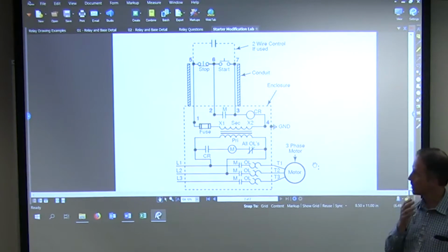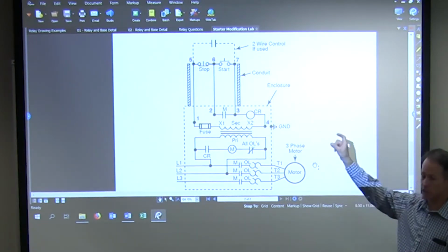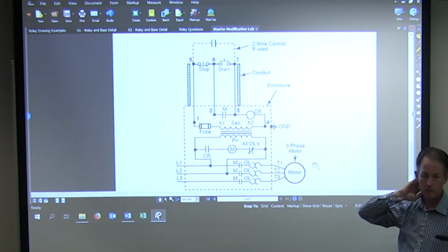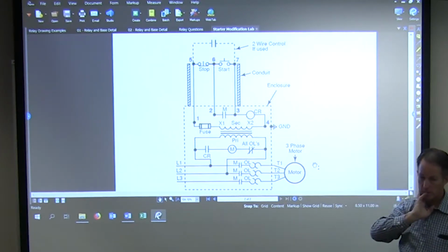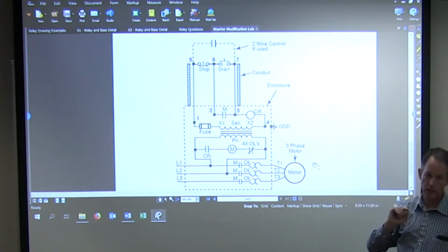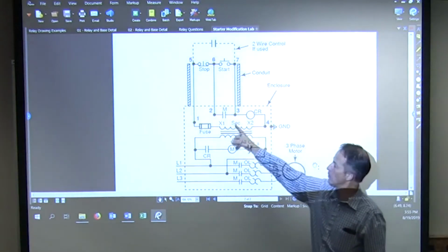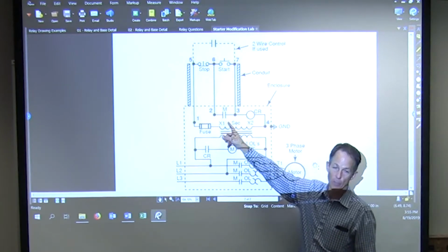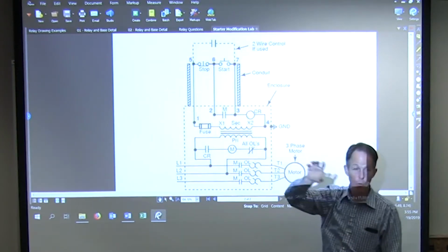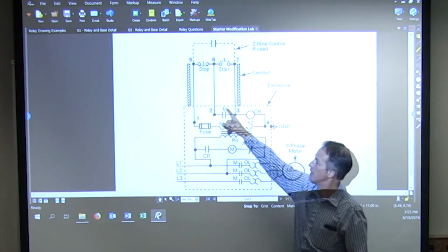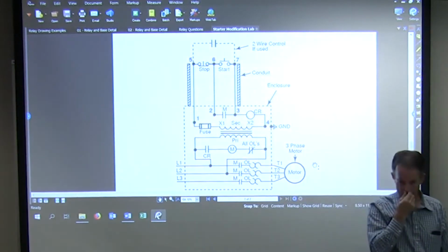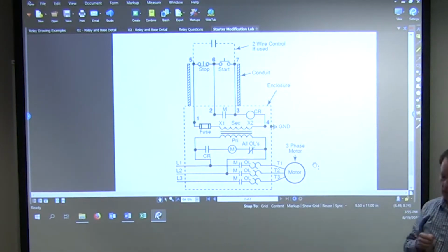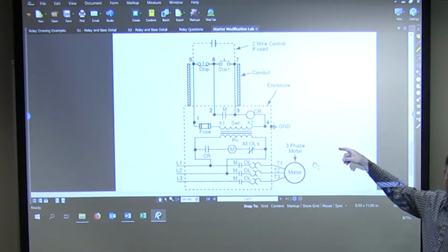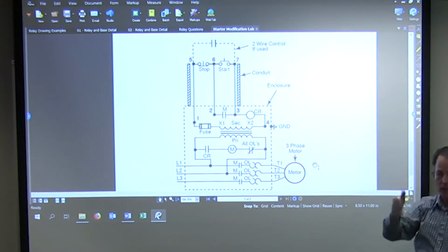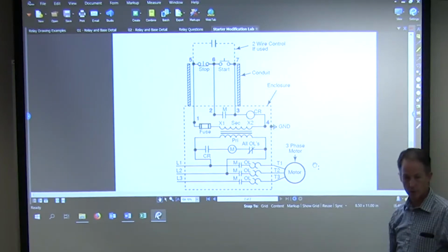So if you could just get away with removing the stop button, you could just de-energize the control and it should just stop - command it off. Not if the stop button was there, because we have a holding contact here. Change the stop button to set up contacts - that's another way we could get rid of it. If you remove the wire from 6, though, it wouldn't work that way. You could also get rid of the holding contact connection - that would be another way to get rid of it so that it would work. So there's a couple ways.